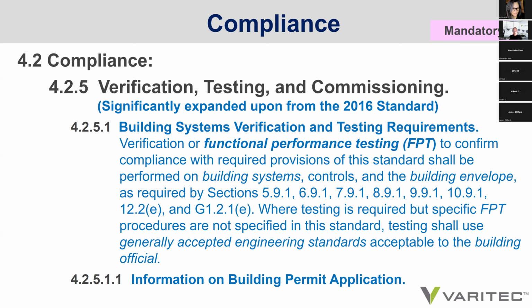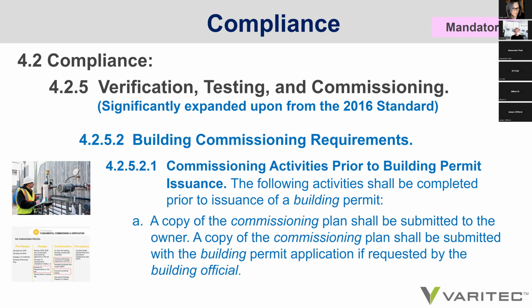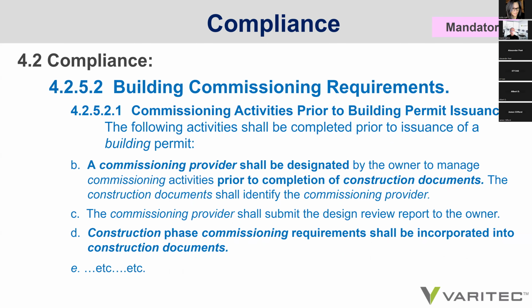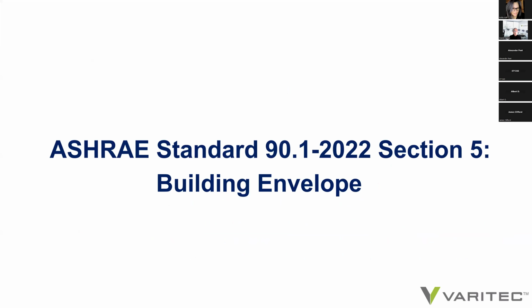on building permit application. And then to enhance building commissioning requirements even further, it goes on to say that commissioning activities prior to the building permit issuance shall be completed prior to the issuance of the permit, and that a copy of the commissioning plan shall be submitted to the owner. So these are all considerable additions to the standard that is going to add some real examination of how we approach commissioning in future buildings. It goes on to say that a commissioning provider shall be designated by the owner to manage the commissioning activities. And also construction phase commissioning requirements shall be incorporated into the construction documents and other prerequisites as outlined in section 4.2.5.2.